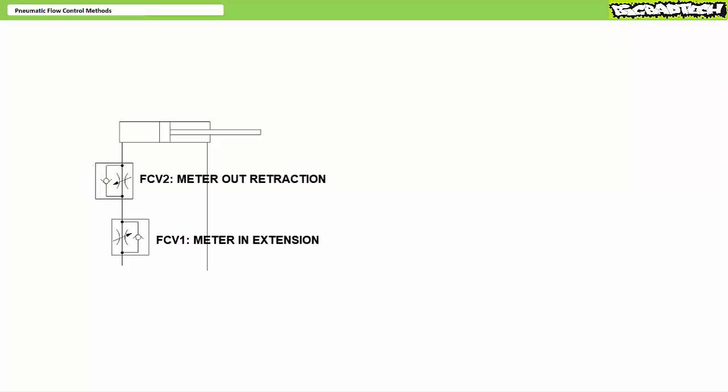Flow control valve two, in contrast, establishes a meter out retraction arrangement by forcing air exhausted from the cap end during retraction through the narrow restriction. During retraction, flow control valve one would be bypassed. One would adjust flow control valve two to dial in retraction speed.